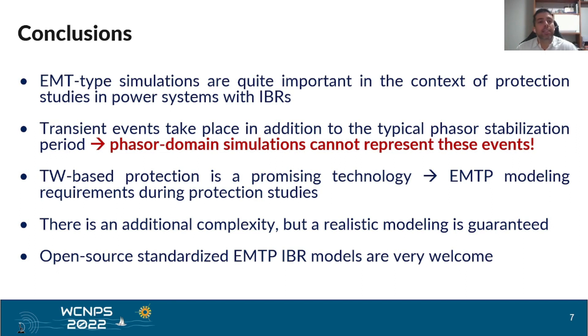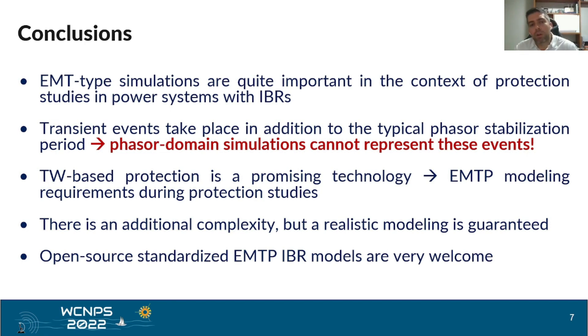As conclusions, we can say that EMT-type simulations are quite important in the context of protection studies in power systems with IBRs. Indeed, there are some transient events that take place in addition to the typical phasor stabilization period, and these transient events cannot be represented by phasor-domain simulations, which puts in evidence the importance of using EMT-type simulations. Another aspect that reinforces the need for EMTP modeling is technologies like traveling wave-based protection, which require EMTP to analyze these protection functions. We recognize that there is an additional complexity when using EMTP, but realistic modeling is guaranteed. In this sense, open-source standardized EMTP and IBR models are very welcome, because we expect EMTP to be more and more used in protection studies for power systems with IBRs.